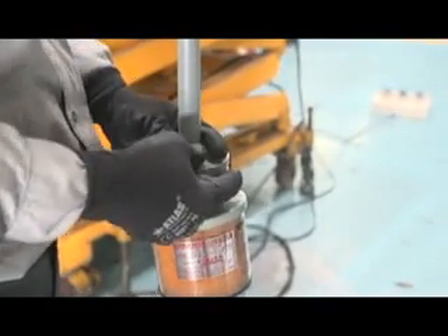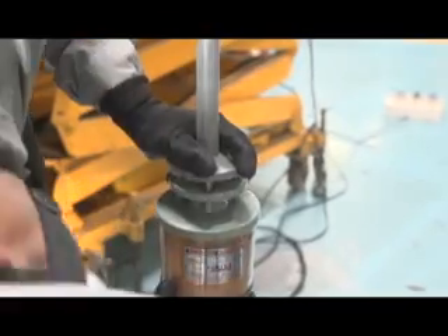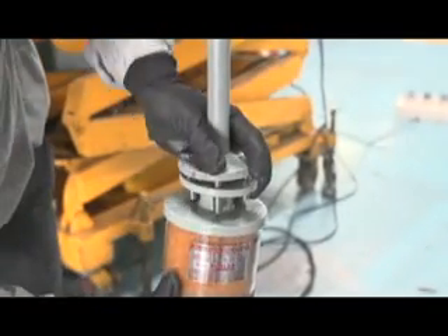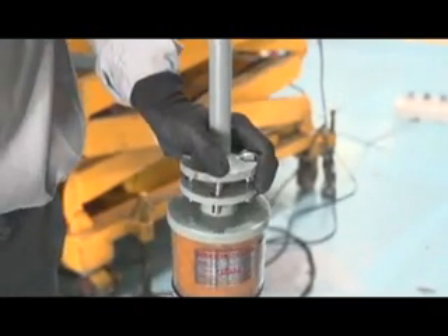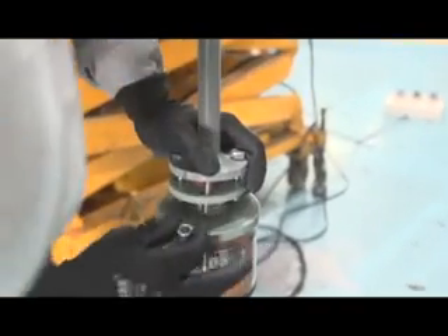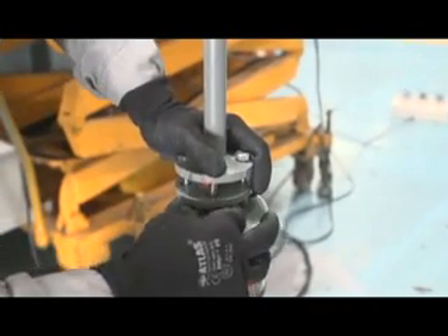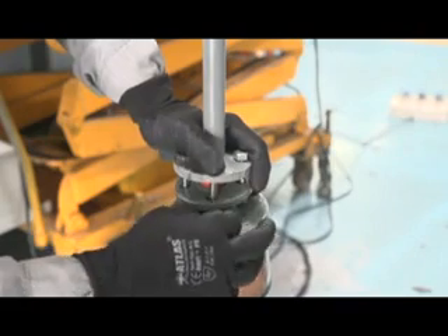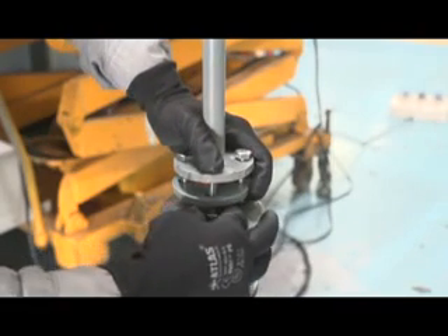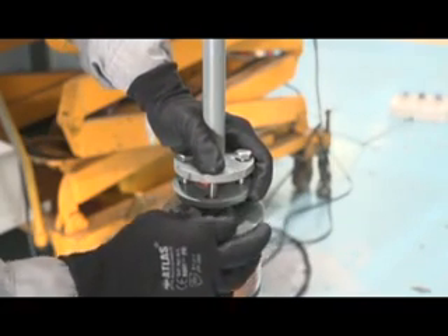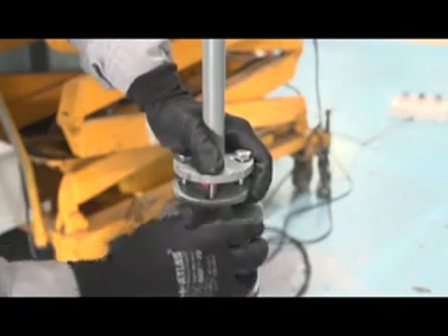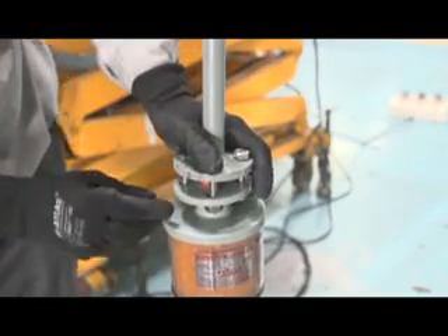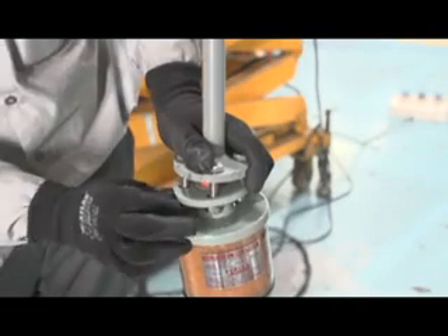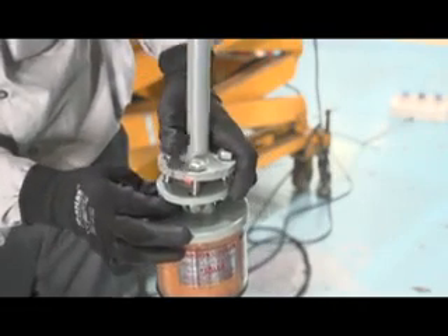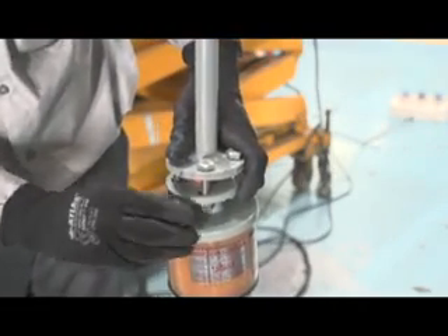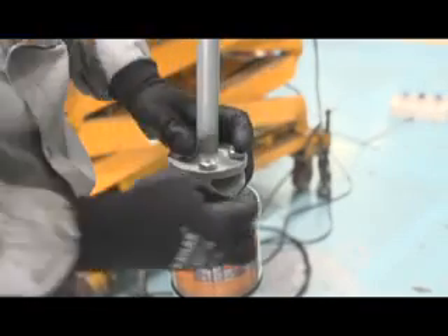When air passes through these crystals in the breather, the moisture of the air is absorbed by them. Therefore, the air that reaches the conservator is quite dry. The dust particles in the air get trapped by the oil in the oil seal cup. The oil in the oil sealing cup acts as a barrier between the silica gel crystal and air when there is no flow of air through the silica gel breather. The color of silica gel crystal is dark blue, but when it absorbs moisture, it becomes pink.